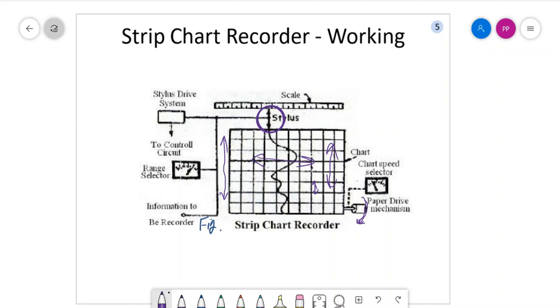The paper drive system should move the paper at uniform speed because if the speed is not uniform then the recording will not be correct. A spring-wound mechanism may be used, but in most cases we use synchronous motors. Now, what are the different kinds of marking mechanisms? Marking on the chart is very important to analyze it visually at a later phase.